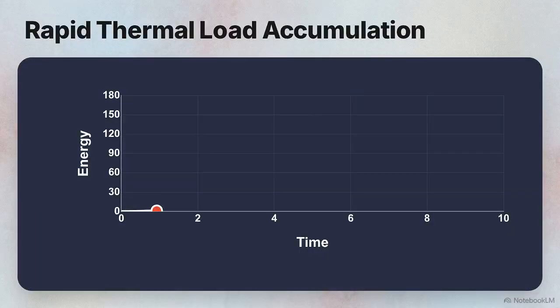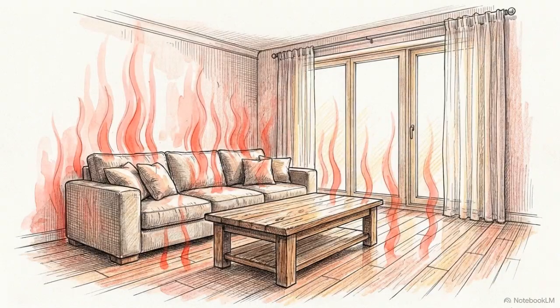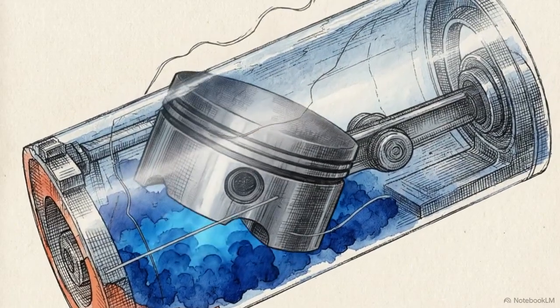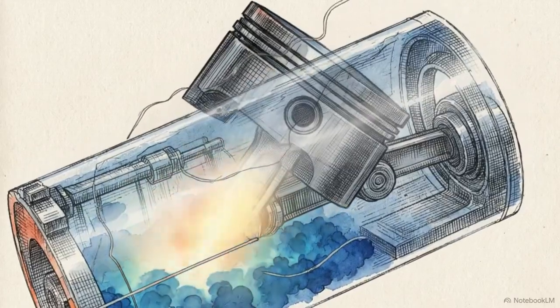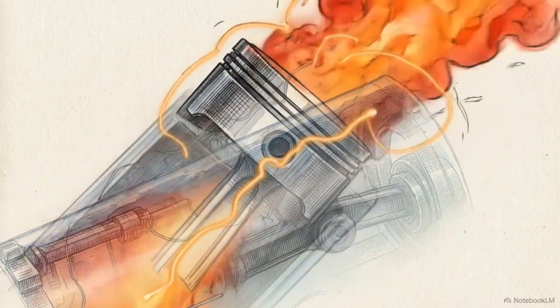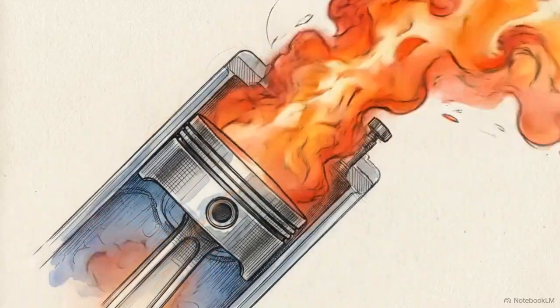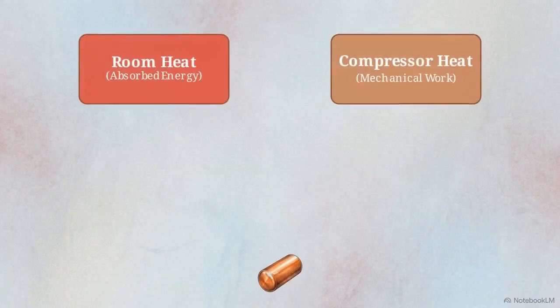To understand the load placed on this component, we have to look at the energy it processes. The first source of thermal energy arriving at the condenser is the sensible heat absorbed from the conditioned room itself. The second source is mechanical. As the compressor pressurizes the refrigerant, friction and mechanical work add a massive amount of heat directly into the vapor. The condenser must process both loads simultaneously.